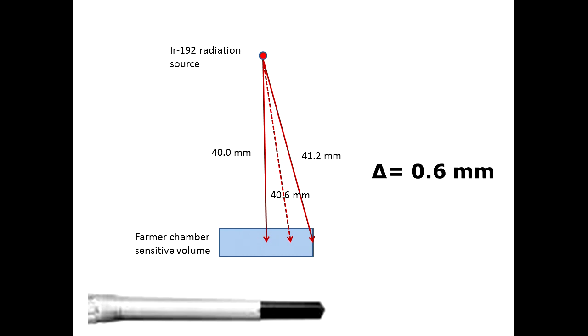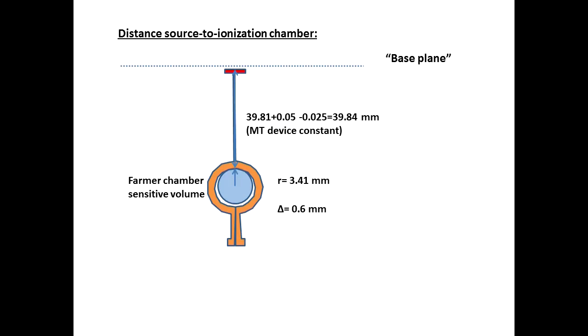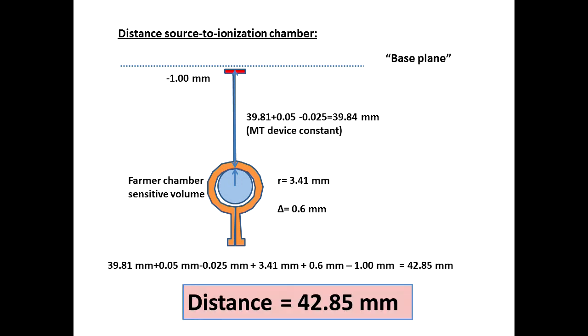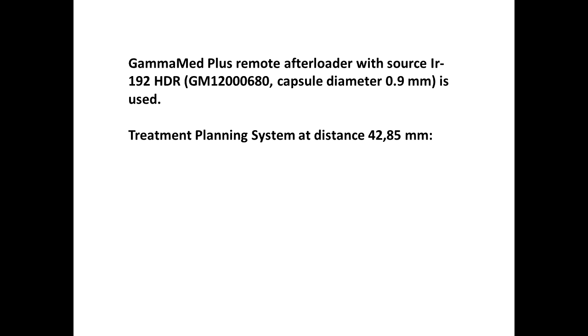For the correction for the longitudinal extension of the Farmer chamber we took 0.6 mm as in the previous presentation. Summation of all these constants and corrections gives us the final distance between the radiation source and the center of the ionization chamber, 42.85 mm. The planning system BrachyVision version 10 gives us for the iridium HDR source a dose rate at a distance of 42.85 mm in the water phantom of 0.4177 gray per minute. It is higher than our measurement by 1.3%.